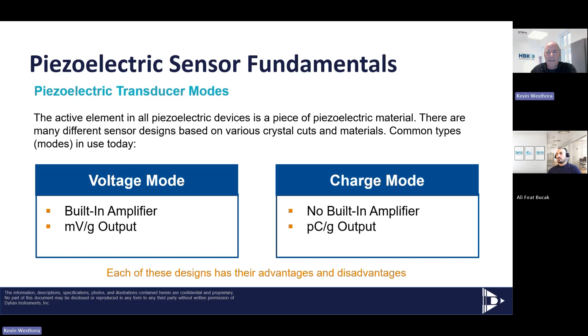That is not the case with DC MEMS accelerometers. With DC MEMS, every accelerometer is different from any other—any Dytran MEMS accelerometer is different from other Dytran sensors, let alone compared to a Kistler accelerometer. So in the DC world, every sensor is different. You need to pay attention to the power supply, the current draw, whether it's single-ended or differential, etc. That's not the case with IEPE—every IEPE accelerometer from any manufacturer is a drop-in replacement for any other, exactly the same, which is unique.